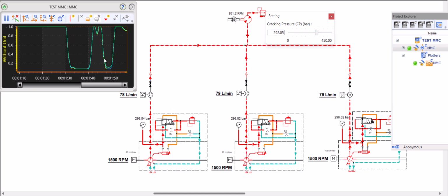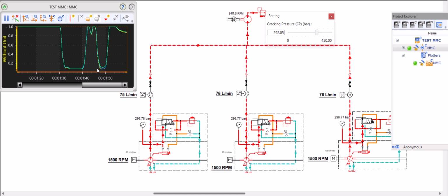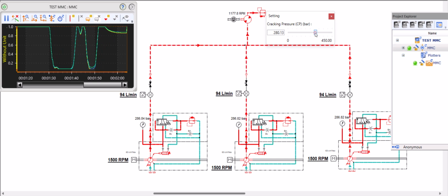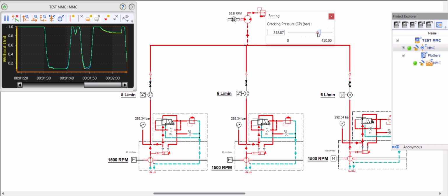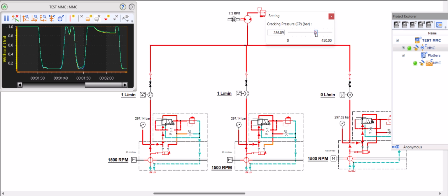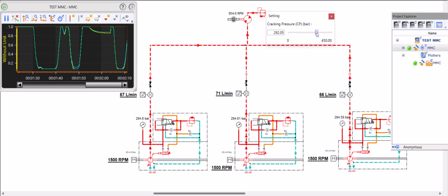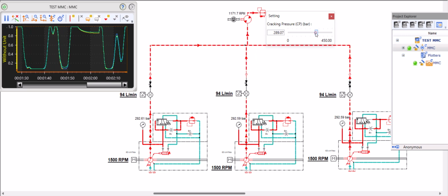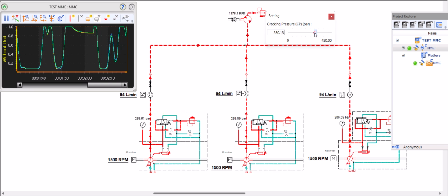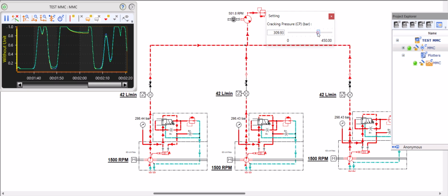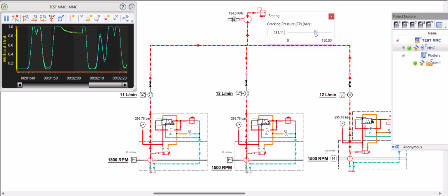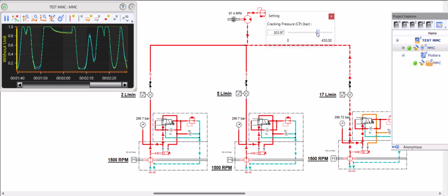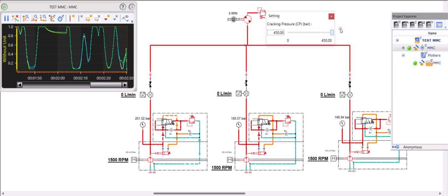You can see at this specific position there is a gap, and there will be differences in the movement of the SwashPlates. This is because of the time taken by the spring setting or spring stiffness of different compensators. You can visibly see that there is a difference. However, this is in an ideal condition. In the industry, we will never find an ideal condition like this. Now I will do a rapid change.